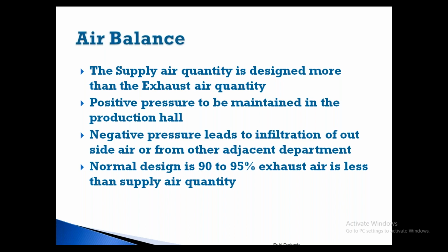For example, in winter season, you're trying to maintain 32 or 34 degrees centigrade inside, and suddenly your exhaust is more. From other windows and openings, it tries to take outside air, which will be chill. If it is 10 degrees or 5 degrees outside, it will take the outside air, so you will not be able to control the desired temperature inside. That is the reason exhaust is given less, supply is more.